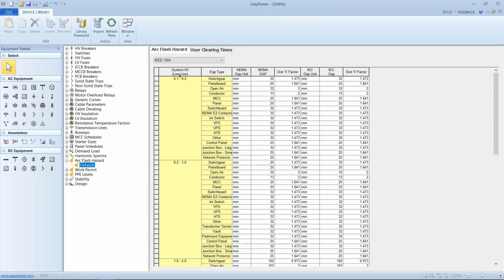These are in the default settings for arc flash hazards. And here under voltage, so we're in the 200 to 1000 volt range, we're comparing motor control centers, which has both an air gap and a distance X factor entry, and selecting small junction box, you'll see that it has exactly the same ratings, air gap and distance X. So the person that did the modeling was able to make this designation without losing any accuracy as far as the calculations for distance X factor.